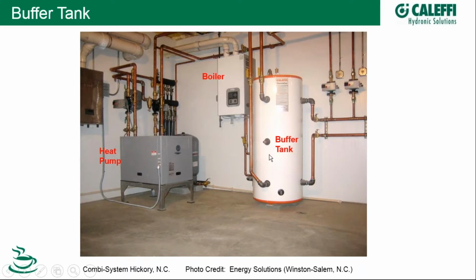We're just seeing the buffer tank that serves the heating side. When there's a call for cooling, there's a little diverting valve up here, and it will send chilled water over to a chilled water storage tank. So back to our example at hand. We've got a heat pump, and in those cold winter months when there's not enough heat in the ground to satisfy the heat demand of the building, a backup heat source takes over.